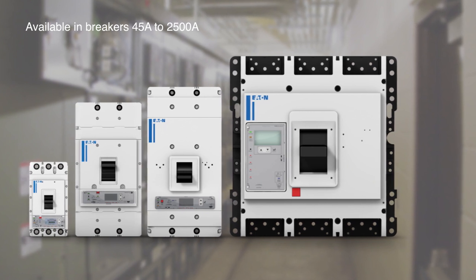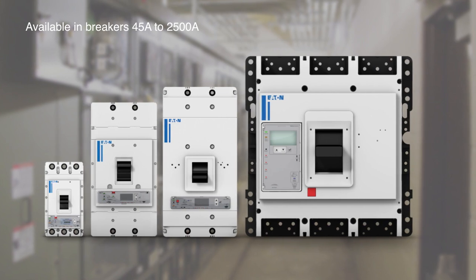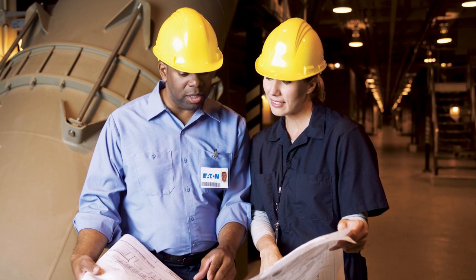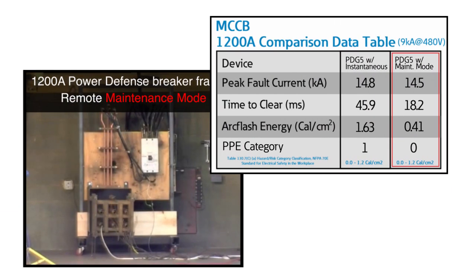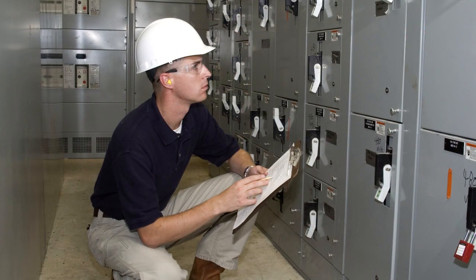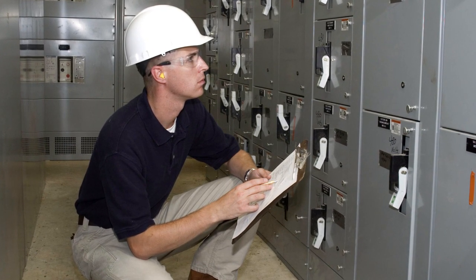Similar results are obtained across other molded case circuit breakers equipped with Power Xpert Release electronic trip units, available in breakers from 45 amps to 2500 amps. To achieve maximum energy reduction, one of the main considerations is to select circuit breakers with the fastest clearing time. The data clearly demonstrates that Eaton's Arc Flash Reduction Maintenance System, or Maintenance Mode, significantly decreases clearing time even below that of standard instantaneous tripping. This results in significant reduction in arc flash energy, minimizing the dangers of arc fault events. Faster clearing time means less arc energy — less arc energy exposure means improved worker safety.